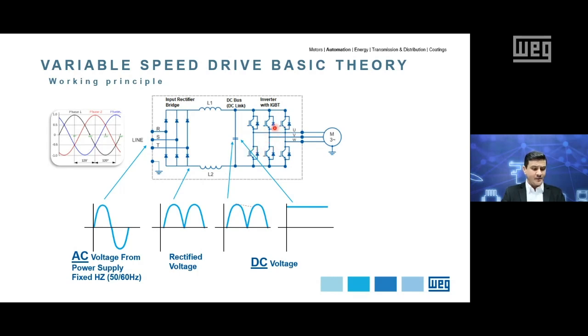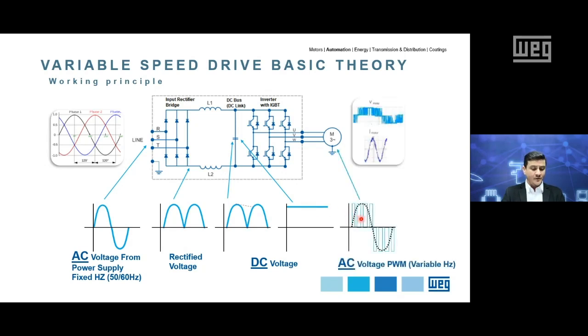Now, the inverter, which is composed of 6 IGBTs, which means insulated gate bipolar transistors, will convert a DC voltage to an AC voltage by using the PWM technique, pulse width modulation. These IGBTs will be switching in such a way that a voltage pulse can be controlled, and as a consequence, a variable voltage and frequency can be generated at the output of the VSD. And since I can vary the frequency at the VFD output, it's possible to vary the motor speed. Comparing with the first equation for the motor speed that we mentioned at the beginning, the parameter frequency can be changed, and as a consequence, I'll be changing the motor speed as well.